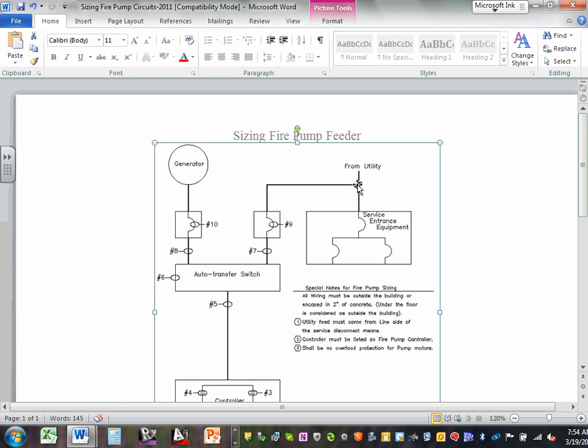So that would be like two mains. One main is going to the fire pump and one main going to the whole building. Then it comes to a circuit breaker, of course, and then it goes to the auto transfer switch. Then you have a generator. From the generator, you have a circuit breaker, and then you go to the auto transfer switch. Everybody understand how we are feeding this fire pump system?